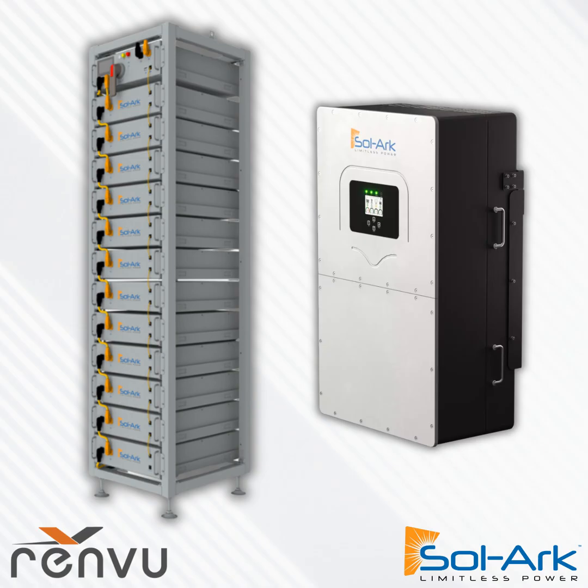What we have is multi-season settings, so you can do beginning of winter, summer, and end of year winter season with different time-of-use settings and grid behaviors. You can shape the reserve capacity of the battery bank and how it feeds into the load or into the grid based on six different time slots across three different seasons.